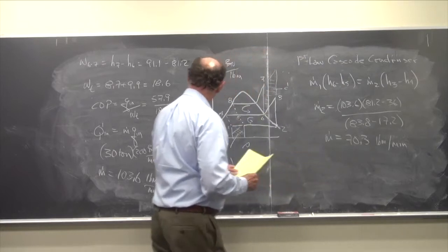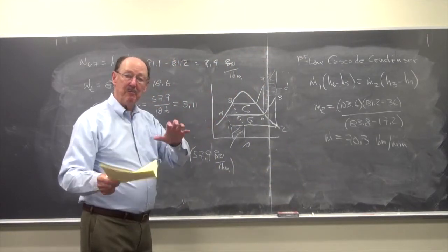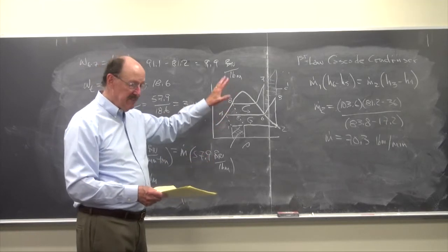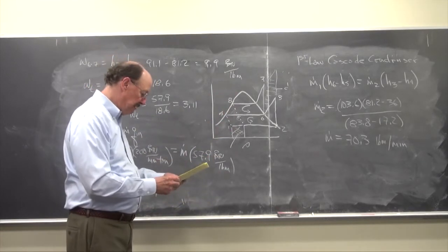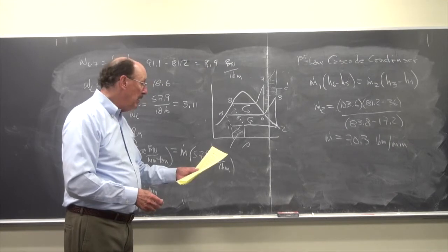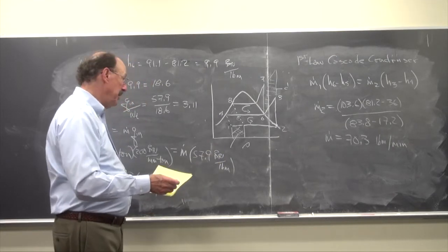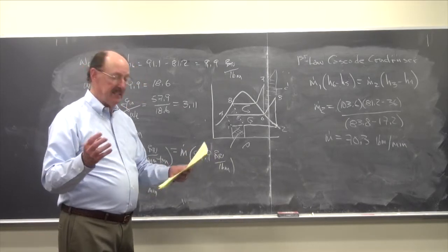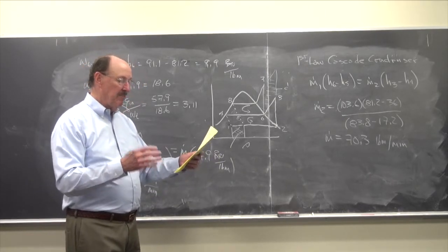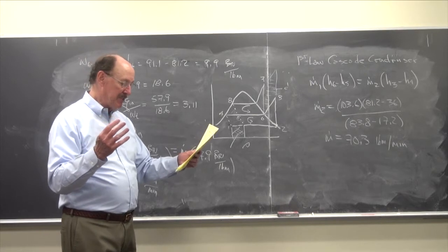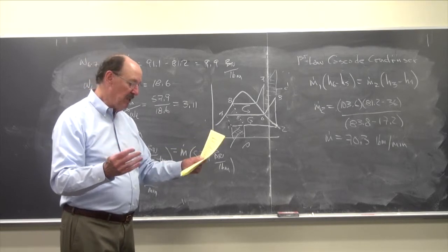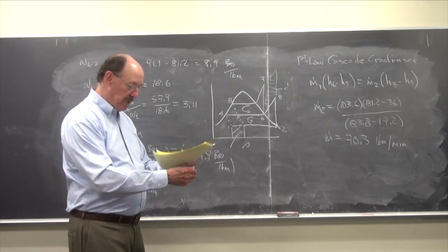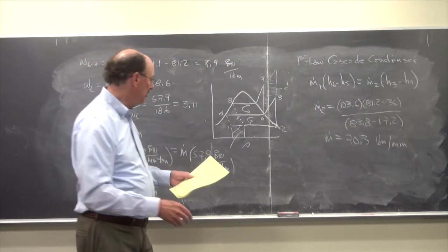So I have the total refrigerant mass flow rate that I need with two compressors, and that is the sum of the two mass flow rates. So I need both of them. And now the total mass flow rate would be 174. And now what I did is I did the same analysis for if we just had one stage of compression, so we could compare and see the two. The COP is dramatically less. So I'll show you what that result is very quickly.